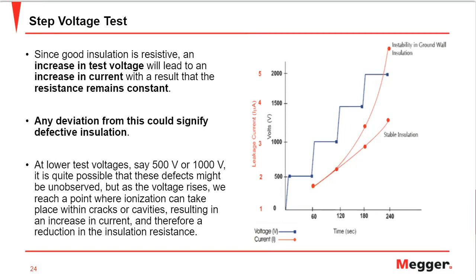And so at lower voltages, when we do the megohm test, we might not be able to ionize the particles, or the cavities or small gaps in the insulation, or the small wear and tear in the insulation, which can give us a false indication of the motor insulation. That's another reason why the DC hypot is tested. In the DC hypot test, the test voltage is higher than the rated voltage of that motor.